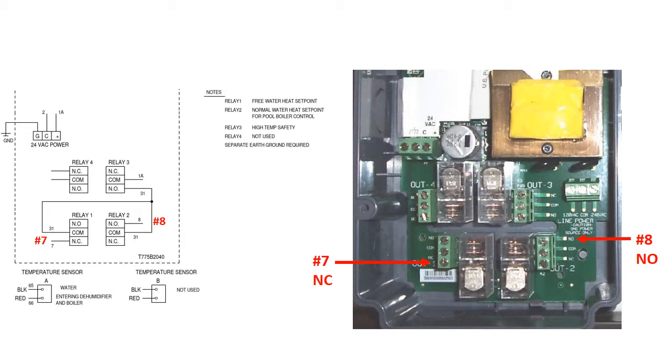Relay 1 is programmed for cooling, and when the free heat set point is reached, the relay will energize, the normally closed contact will open, and no more heat will be added to the pool water.